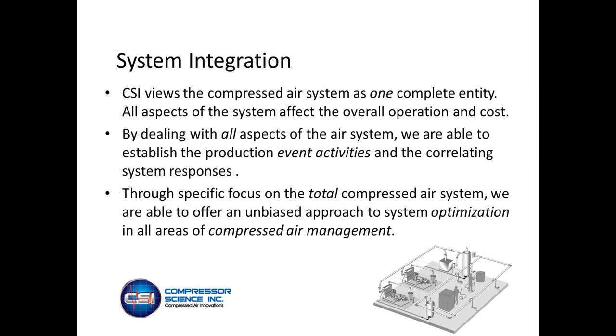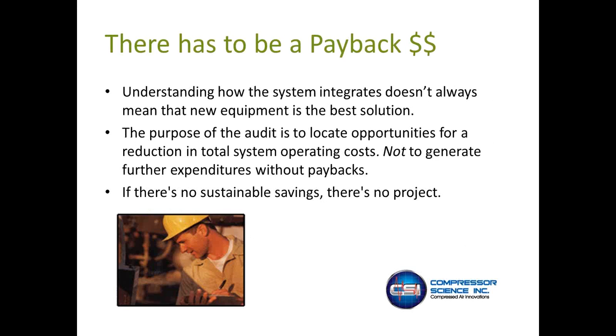So by focusing on the total compressor system, we offer basically an unbiased approach to looking at the whole system optimization. Not every audit that we do results in the sale of a new compressor. Sometimes we're looking at changing piping, adding storage, adding controls to existing compressed air systems, whatever is going to help optimize that system and reduce the power consumption at the machine is what we're after. Again, there has to be a payback.